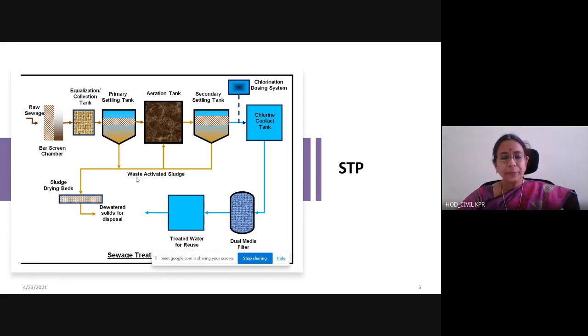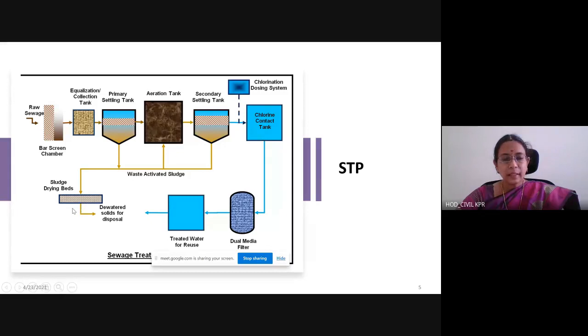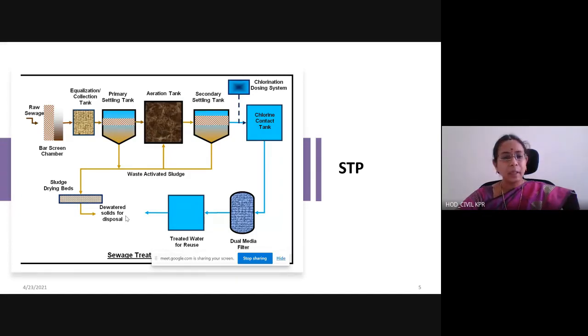After filtration, the wastewater is taken out for reuse — that is, the treated effluent is taken out for reuse. Waste activated sludge is taken out and sent to the sludge drying beds. Here, dewatering is done since the sludge will contain liquid. After dewatering, the dry sludge is let out for disposal — either to sludge drying beds, to a landfill, or sometimes used as manure if it does not contain any harmful content.